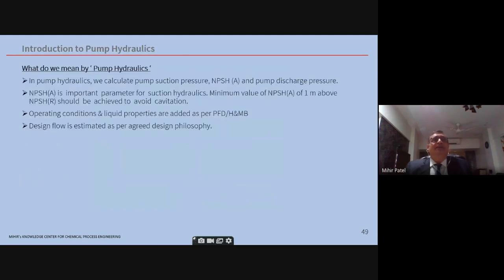Then, introduction to pump hydraulics. Now hydraulics can be of many types. Gas hydraulics are there, vacuum hydraulics are there, two-phase hydraulics are there, pump hydraulics are there. Here I'm just covering pump hydraulics in brief. In the advanced course, I'll be going very deep into this subject also. So in pump hydraulics, we calculate the pump suction pressure, NPSHA, and pump discharge pressure.